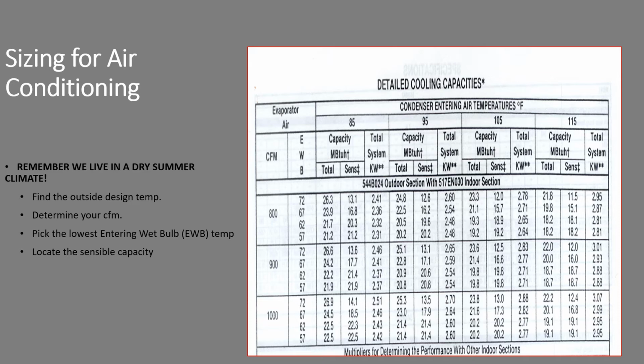Sizing for air conditioners. Every manufacturer presents their detailed capacity just a little bit different than every other manufacturer, making our lives sort of complicated. But regardless, the process is usually the same. You find the outdoor design temperature. In this case, it's up here near the top. You determine your CFM, and this happens to be for a 2-ton system. You start at 800, you go to 900, you go to 1,000. Please notice it doesn't go down to 700 or 600.